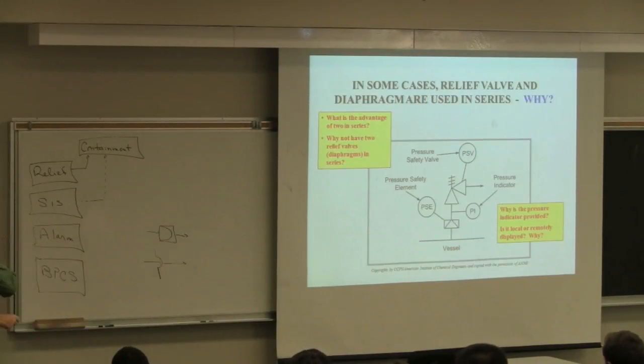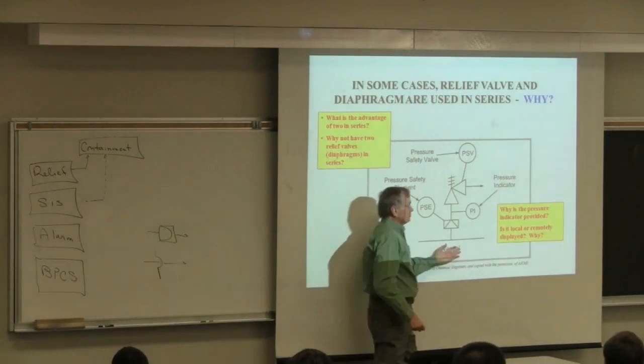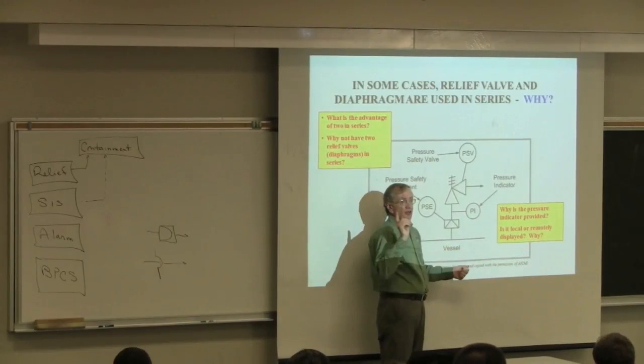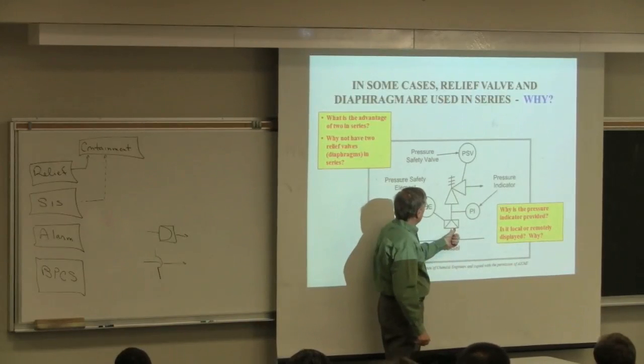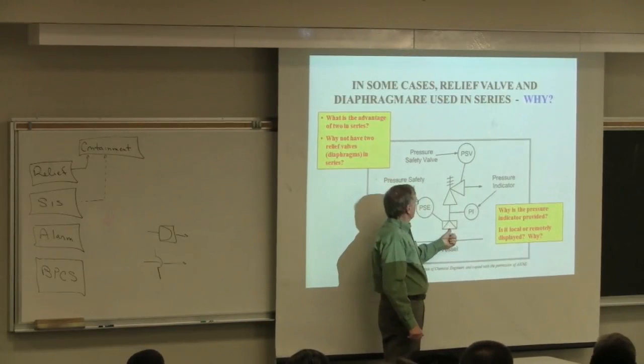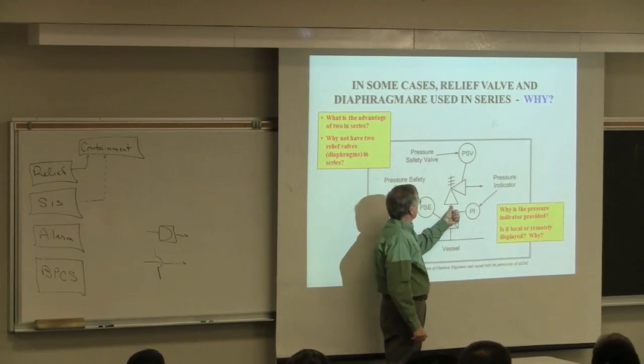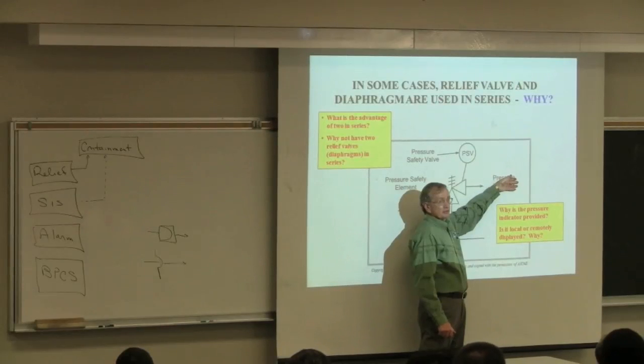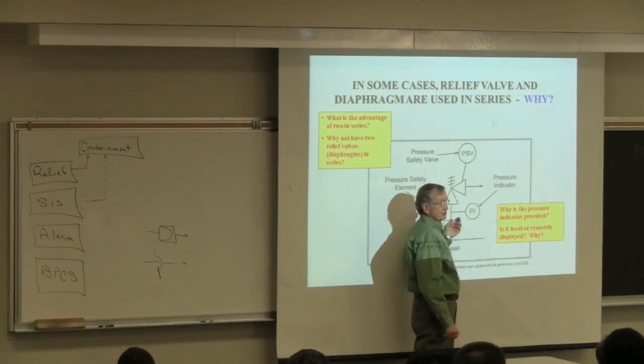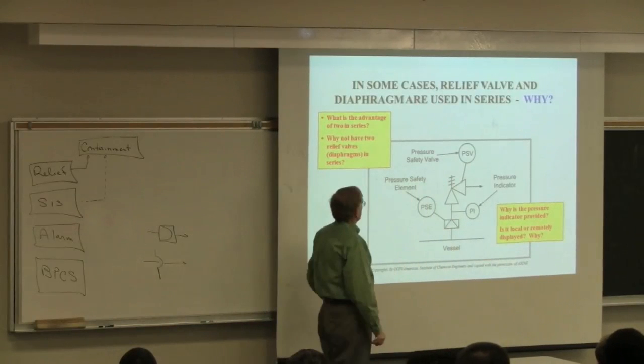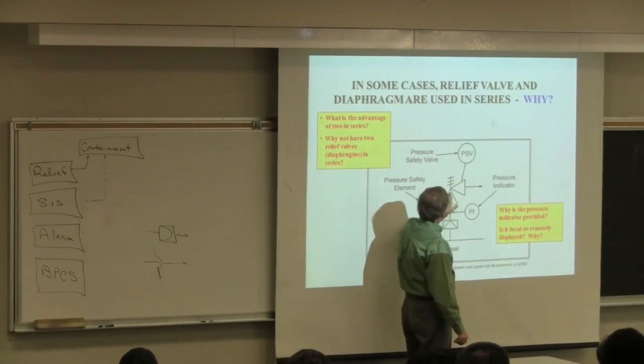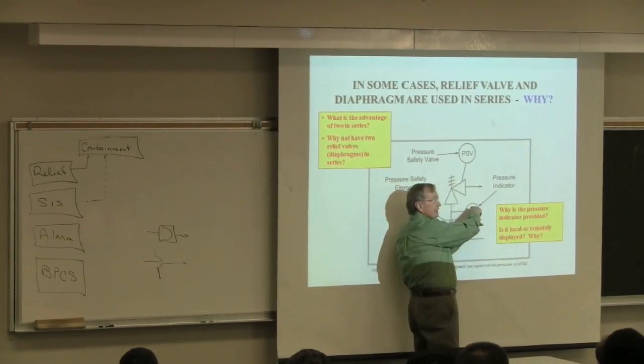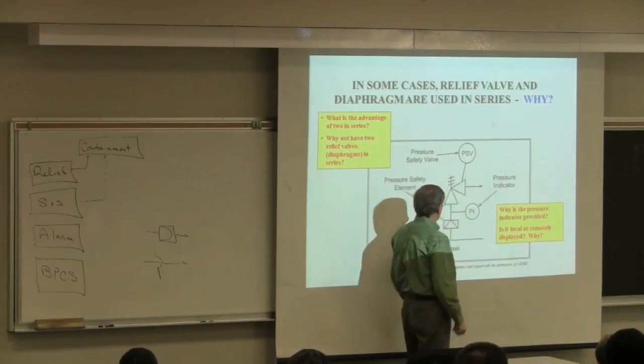Here's an important design: a vessel with a burst diaphragm, followed in series by a safety valve, then a release to a container, with a pressure sensor between the burst diaphragm and the safety valve. This looks strange—two devices in series. The vessel is a reactor making a polymer by emulsion polymerization. Why would you use this design?